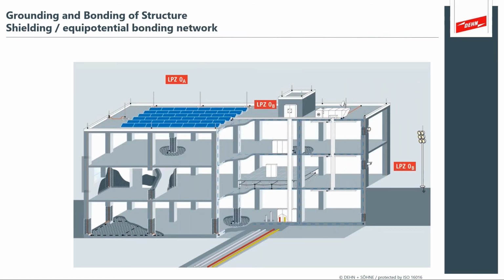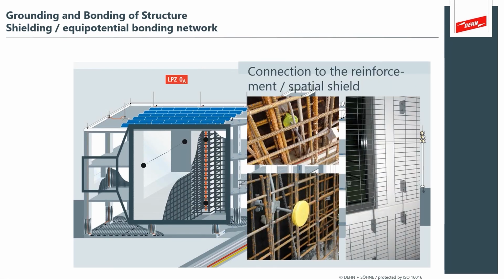So when you're looking at a system, this bonding and equipotential system also provides shielding as well as equipotential bonding. So what's important here is you might have these mesh systems embedded around the structure. And this provides what looks like a Faraday cage, an electromagnetic shielding aspect. And that's what's important about the bonding. You need to bond and ground that system and earth that system to provide suitable electromagnetic shielding.